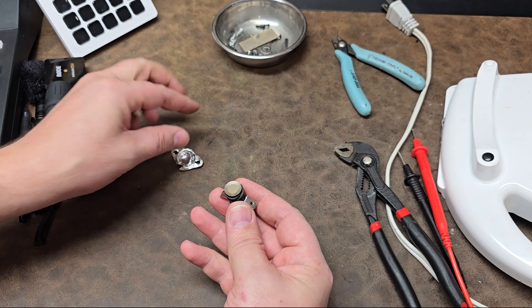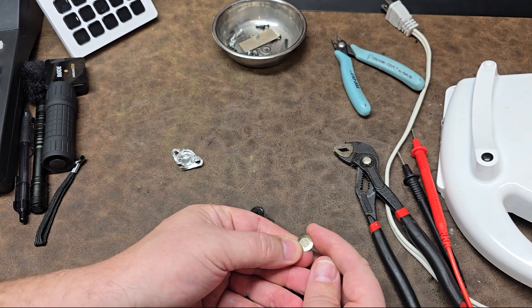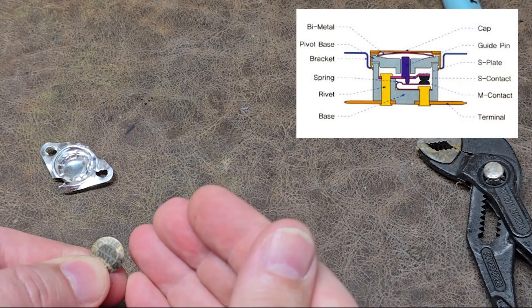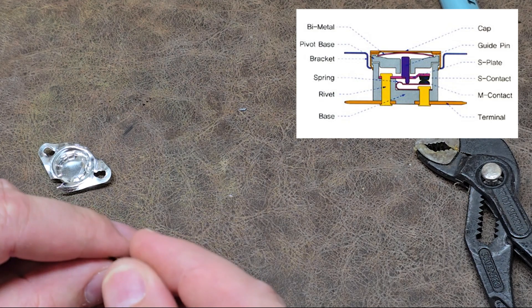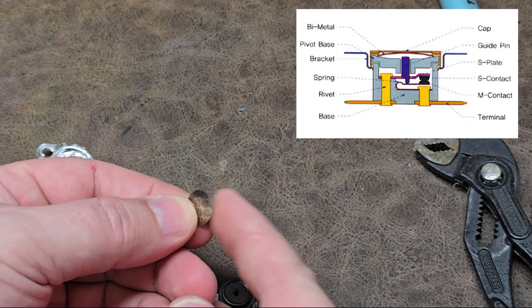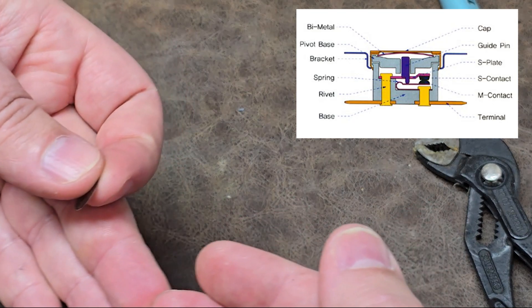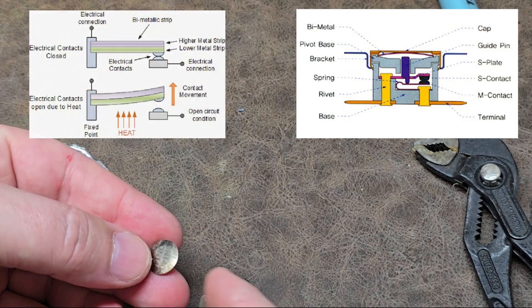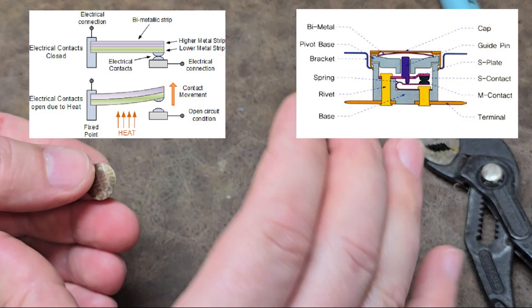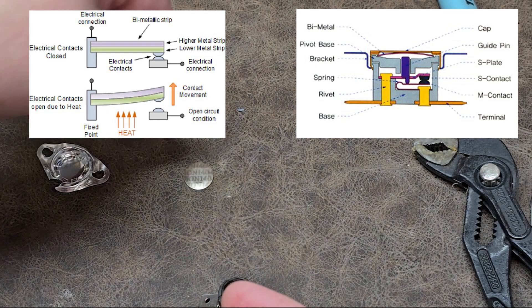I have this guy taken apart so you guys can see the diaphragm that's underneath it. It has a bimetallic diaphragm and you can see on the diaphragm it says that it has 140 degrees. See that? It says 140 on it. So what they do is they press or they stamp a couple different metals one on top of each other, and then it has a natural spring loaded shape to it. And as it heats up, the spring is going to pop the opposite direction and it's going to happen very quickly and it's going to happen at a very specific temperature. You can see here it says it's at 140 degrees. Now the angle of the curvature and the diameter, it's all going to affect when this guy snaps. So you can see it's set at 140 degrees.